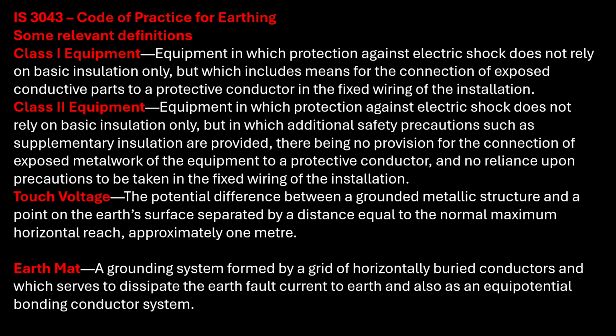The class 1 equipment in which protection against electric shock does not rely on basic insulation only, but which includes means of the connection of exposed conductive parts to a protective conductor in a fixed wiring of installation. In the class 2 equipment in which protection against electrical shock does not rely on basic insulation only, but in which additional safety precautions such as supplementary insulations are provided, there being no provision for connection of exposed metalwork of the equipment to a protective conductor and no reliance upon precautions to be taken in the fixed wiring of the installation.